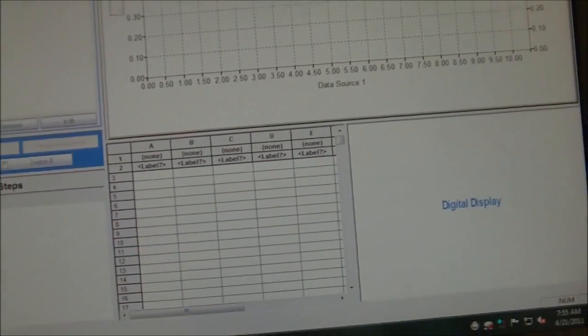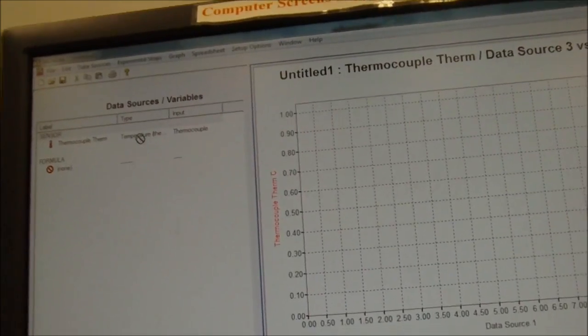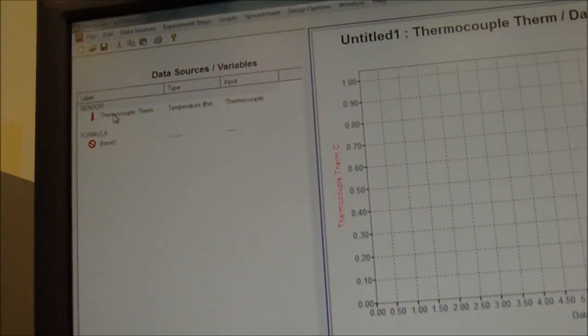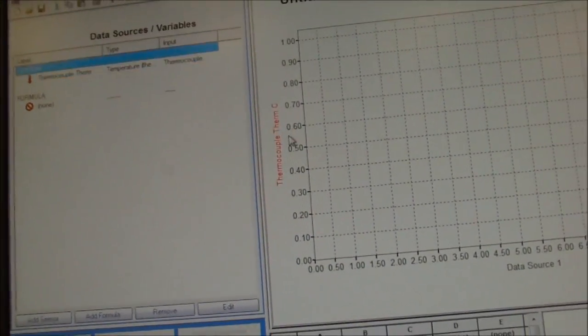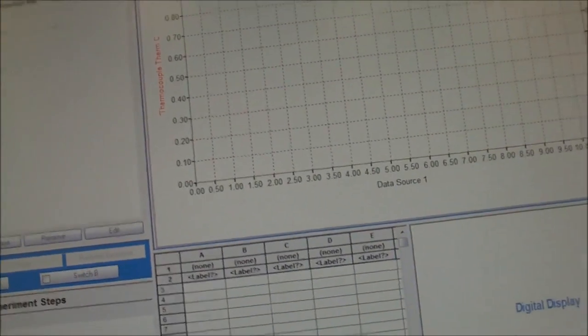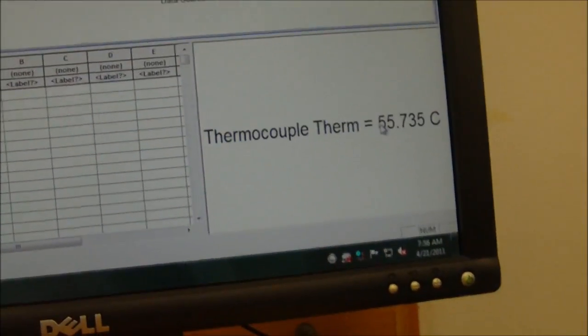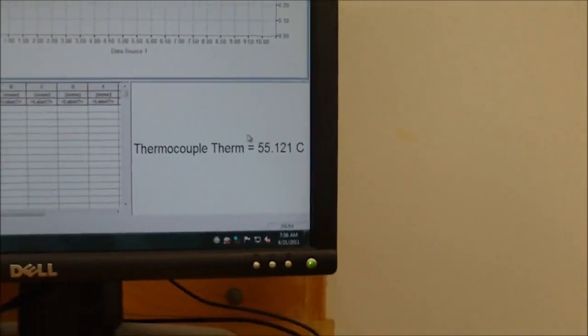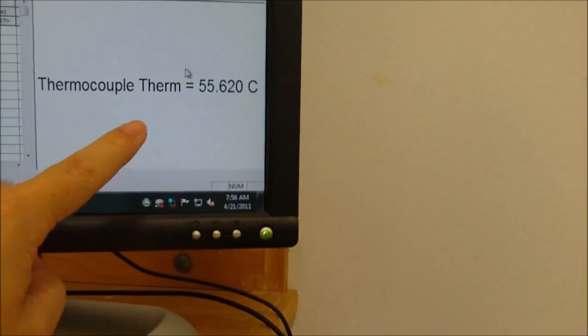We can take that thermocouple, put it here. We could drag the thermocouple, I'll do that again. We take this thermocouple here, we drag it down onto our y-axis. We take it from our y-axis, we can also drag it over to here, and it should be telling us the temperature, and it is telling us the temperature of that hot water right now, right? And that's good. Now that that's there, we can always monitor and verify that whatever the temperature is, it's reasonable, right?